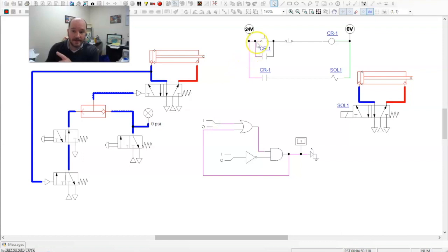When I activate this, it's like pushing this start button. When I let it go, it's disengaging the start button, yet the output is still true, because power comes in through here. So that is the digital version of a start-stop station, commonly referred to as a three-wire control sometimes, and a motor starter. There are a lot of different names for it out there.